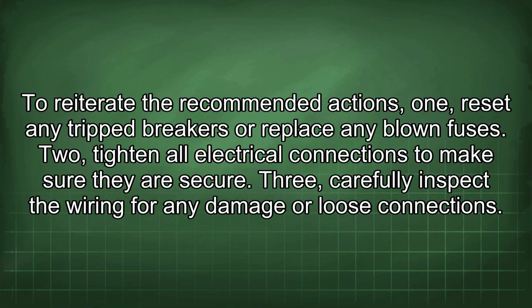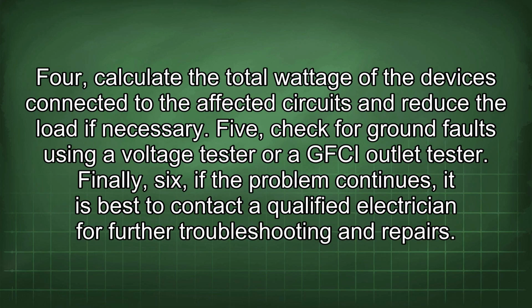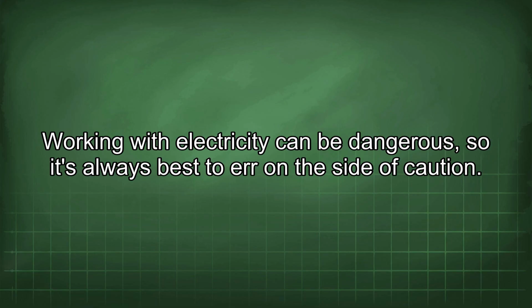To reiterate the recommended actions: 1. Reset any tripped breakers or replace any blown fuses. 2. Tighten all electrical connections to make sure they are secure. 3. Carefully inspect the wiring for any damage or loose connections. 4. Calculate the total wattage of the devices connected to the affected circuits and reduce the load if necessary. 5. Check for ground faults using a voltage tester or a GFCI outlet tester. Finally, 6. If the problem continues, it is best to contact a qualified electrician for further troubleshooting and repairs. Working with electricity can be dangerous, so it's always best to err on the side of caution.